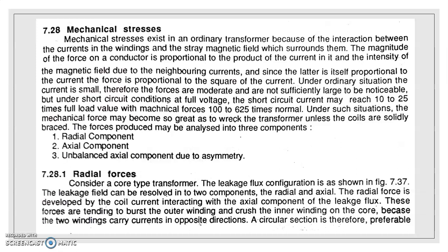Because the current appears 10 to 25 times the full load, the forces again appear as the square of that. It means 100 to 625 times the normal forces.